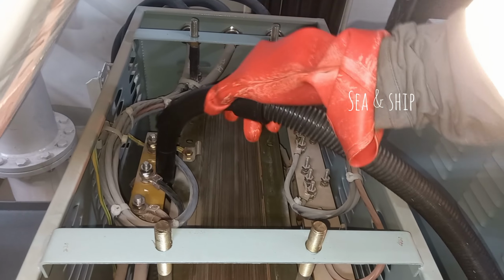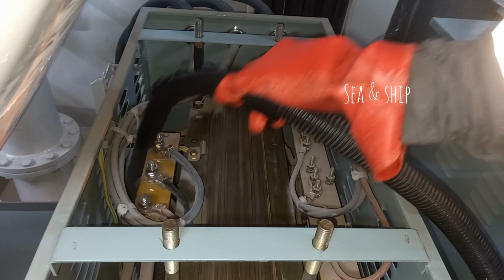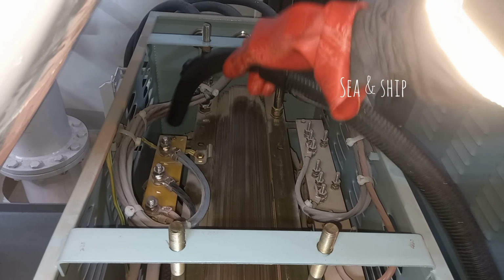Finally, before energizing, make sure all tools are removed, covers are properly fixed, and the area is clean. Then switch on the transformer and monitor voltage, current, noise, vibration, and temperature.